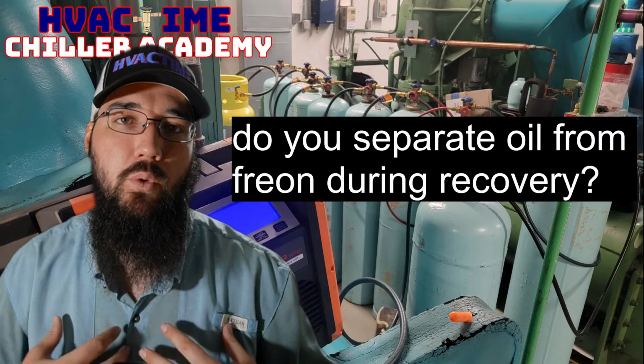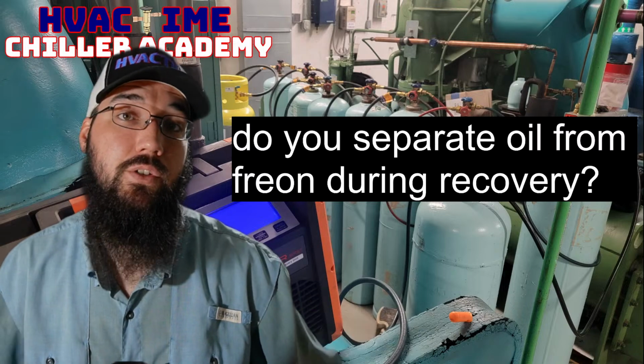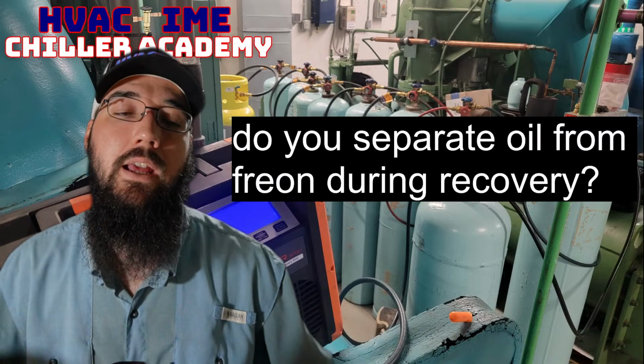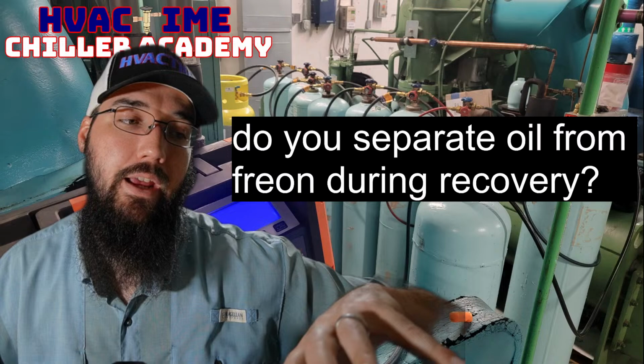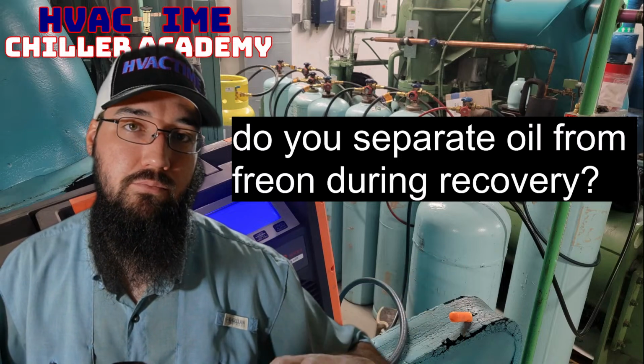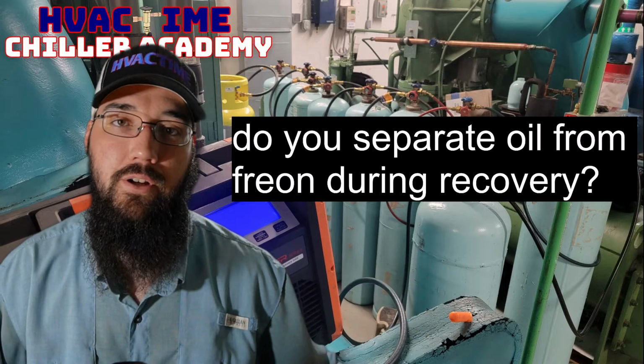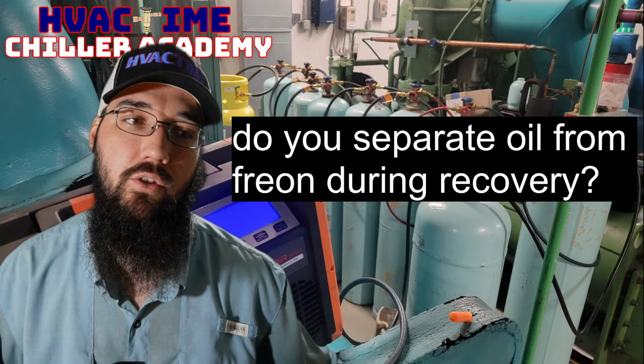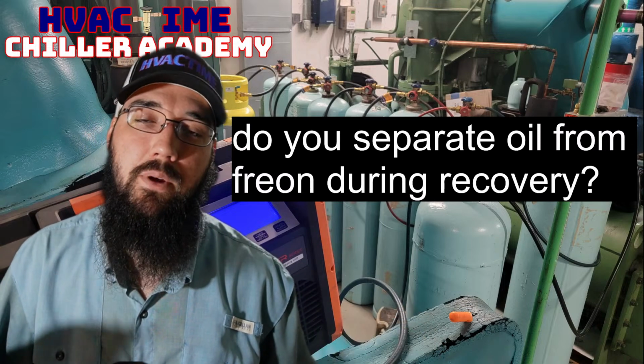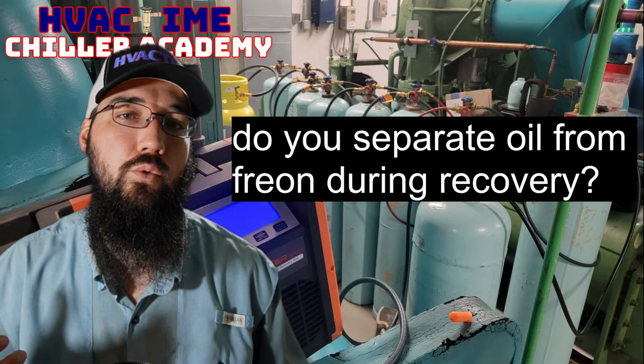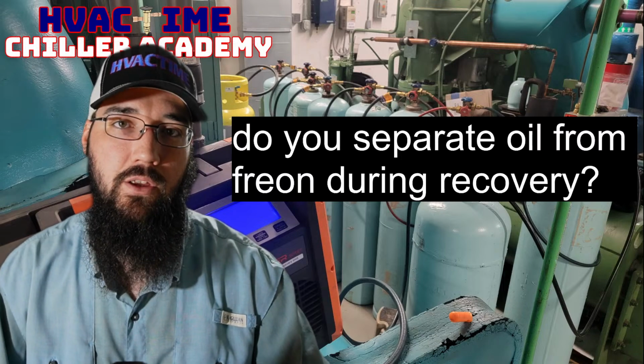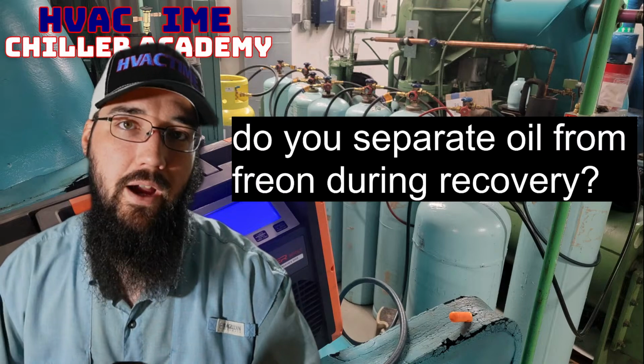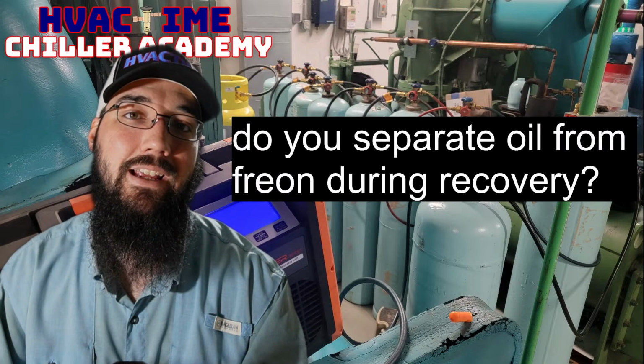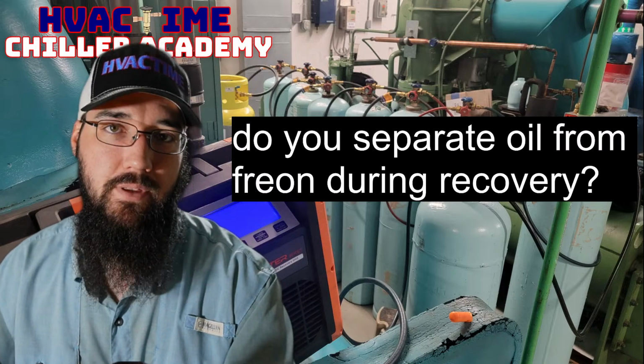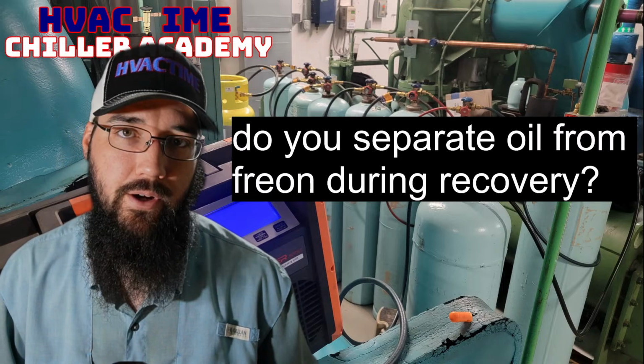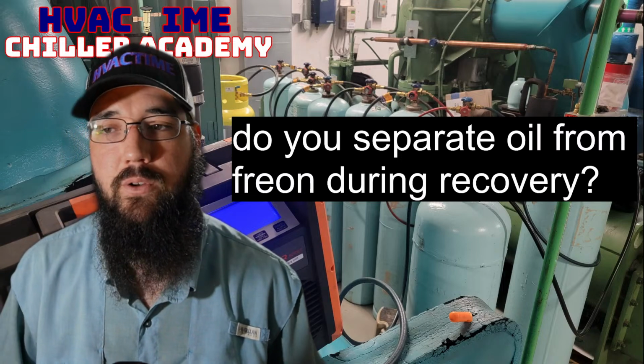The way I've always done that is we'll just tip the cylinder over when we're done, and drain whatever is in there into a bucket or a container of some kind and dispose of it accordingly. So that is just one method of trying to mitigate that. If you have a system that has migrated and you've got a lot of oil in that refrigerant, that's an effective way of separating the refrigerant from the oil.